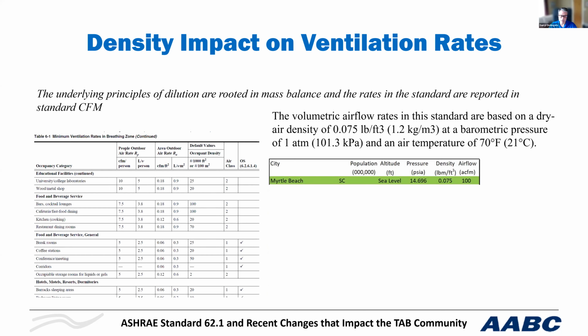And so the engineer doesn't have to correct for this. And it's perfect. However, for any elevation change above that, there should be an engineering correction, because the ventilation will then be under what is expected of the standard. And this is a minimum standard. This is a minimum ventilation. And TAB is only going to balance to what's on the design documents. They're not going to say, hey, you guys are doing it wrong. No, that's what it is.